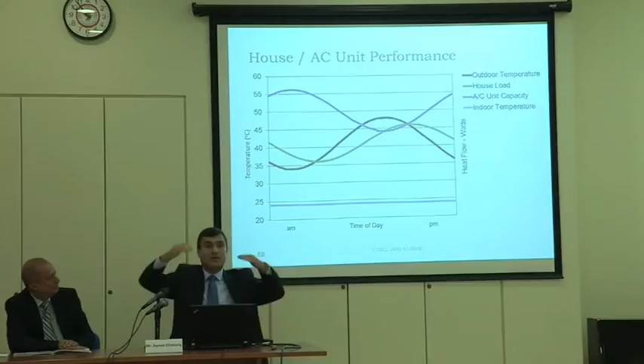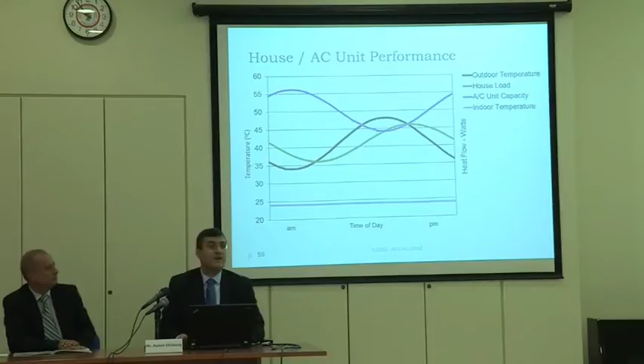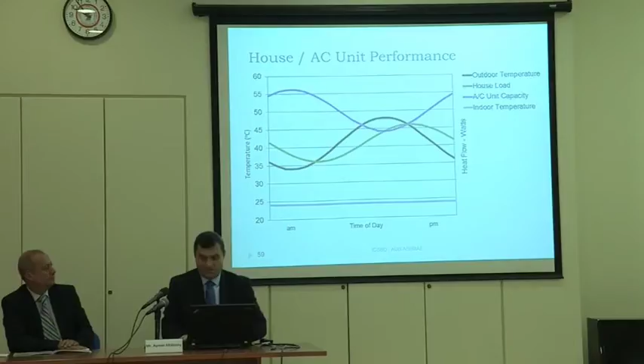However, when you do the cooling load of the house, you could see that the cooling load versus time does change. And there is this time lag that I'm talking about between the maximum temperature outside and the cooling load of the house. So there is a couple of hours time lag. Putting the cooling load on the curve again, you could see now really the problem that you may have with cooling if you keep it at 46 for Kuwait, for example, is only very small, and it's only half an hour a day. So to set design conditions to 48 means you're going to shift all this load up, more energy will be needed, and in Kuwait, 70% of the energy goes to cooling, so Kuwait will need probably 75% for the cooling load and so on.